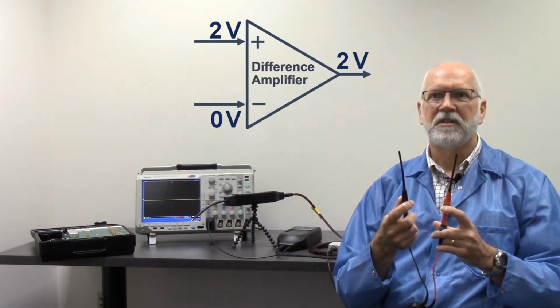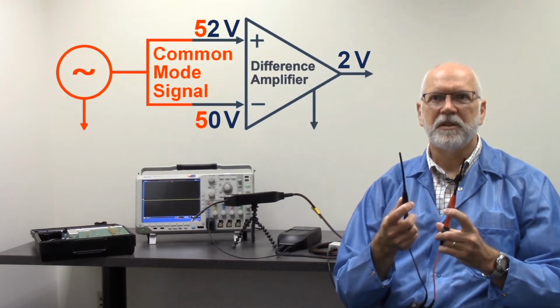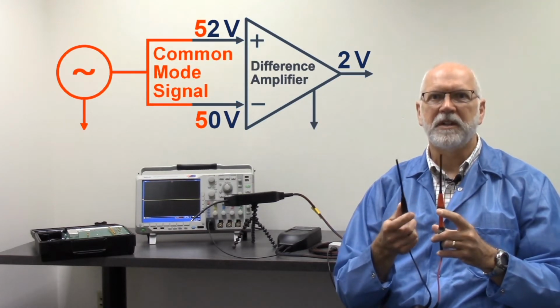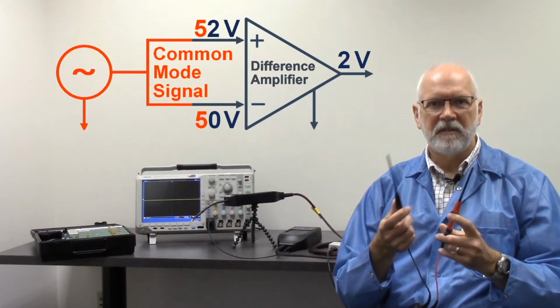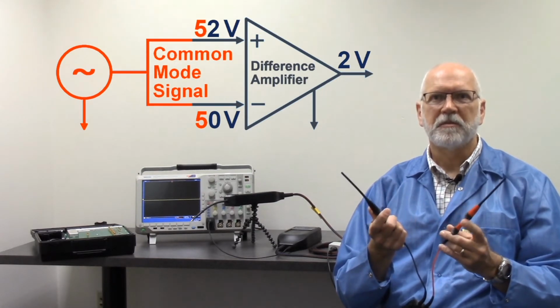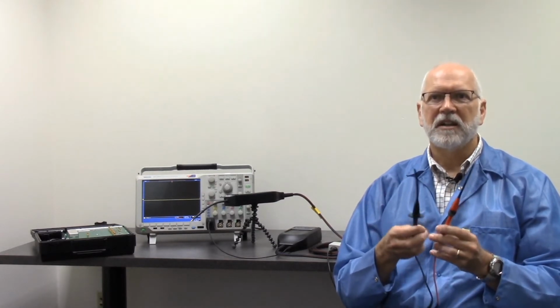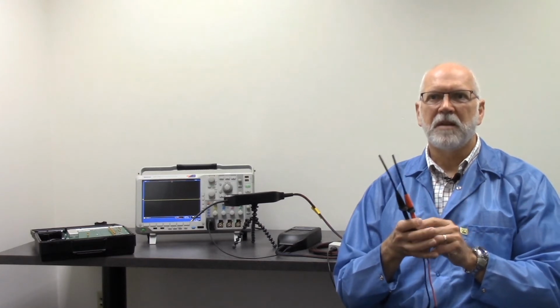So if I'm trying to measure 2 volts differential when there is 50 volts of common mode voltage, the probe needs to display the difference between 52 volts and 50 volts, which is 2 volts. The ability to reject the common mode signal is the amplifier's common mode rejection ratio.